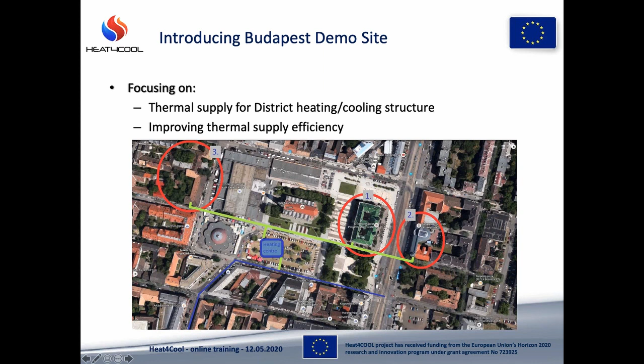If we look at the layout of the site, we have to double check the flows, since this is our heat source. In summer, for example, the flow is much lower at night, because people don't use their washing machines, dishwashers, toilets, and so on as much as in daytime. But we still have to produce heat at nighttime if needed, so we concentrate on the low flows at night, and with some storage we can equalize this for the whole day.